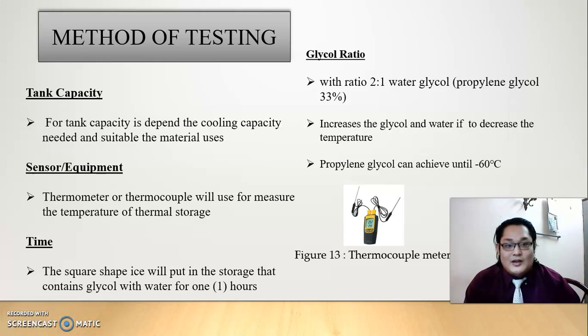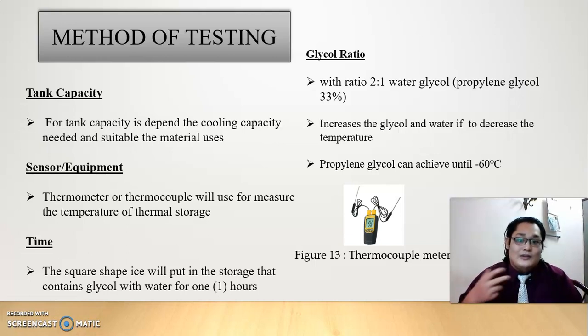Glycol ratio. With a ratio of 2:1 water to glycol, we mix glycol with water, but water is more than glycol. So propylene glycol is 33%. Increase the glycol and water if we want a lower temperature. Propylene glycol can also achieve down to negative 60 Celsius.